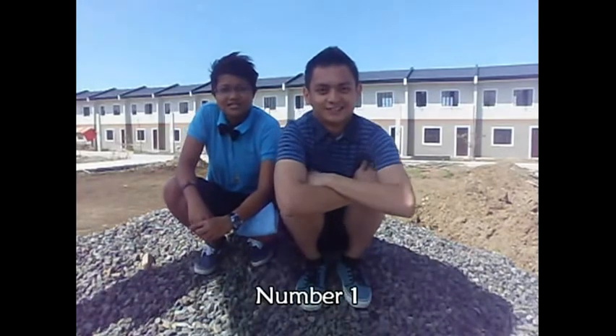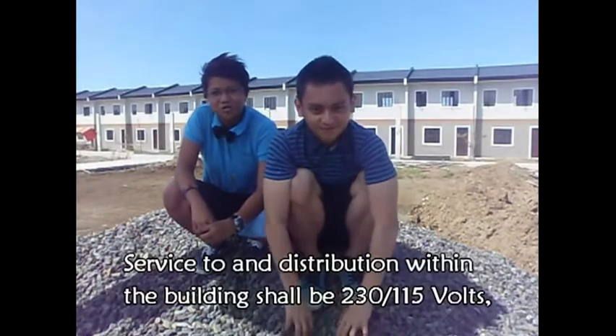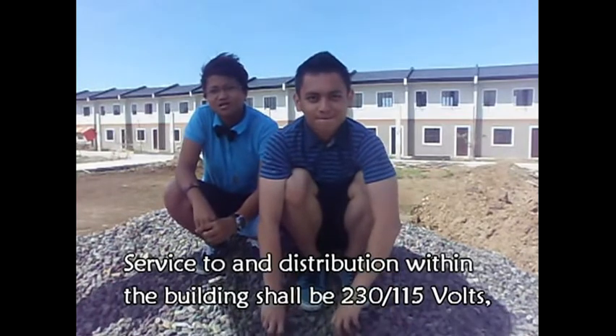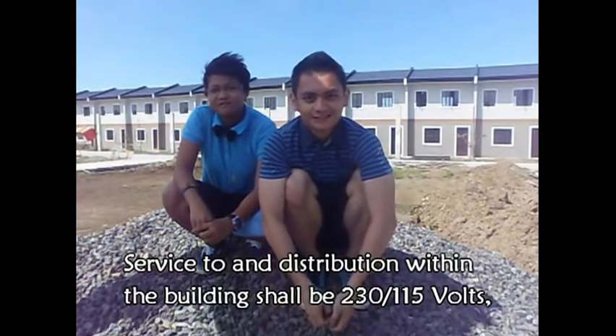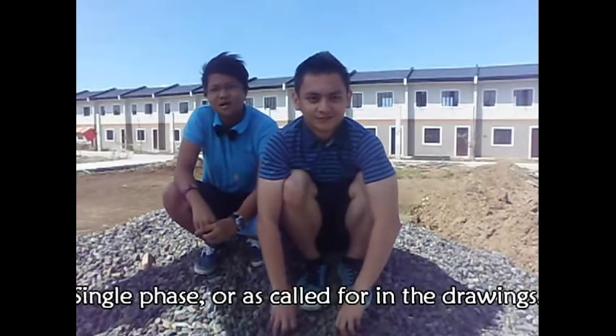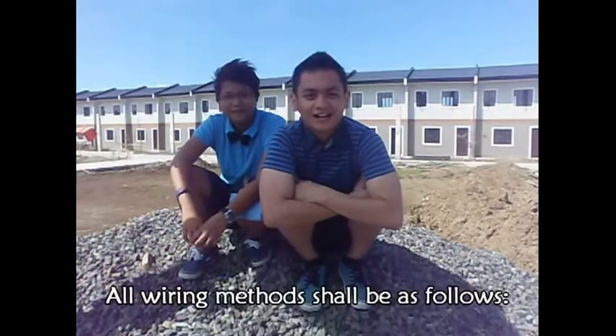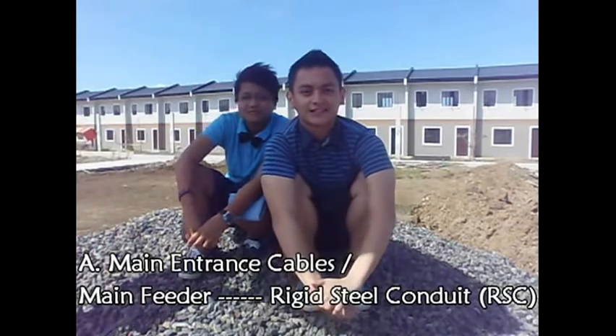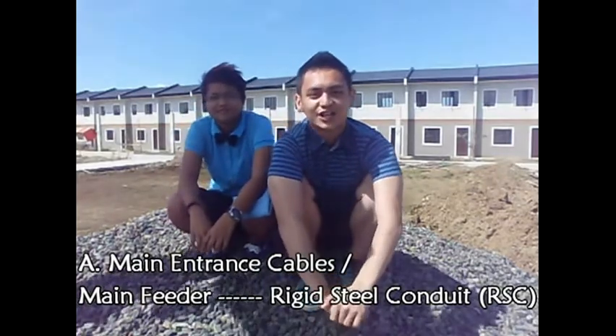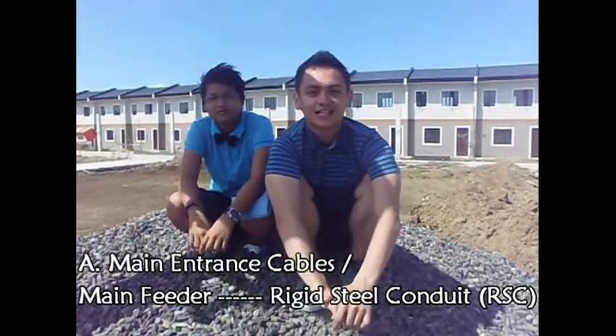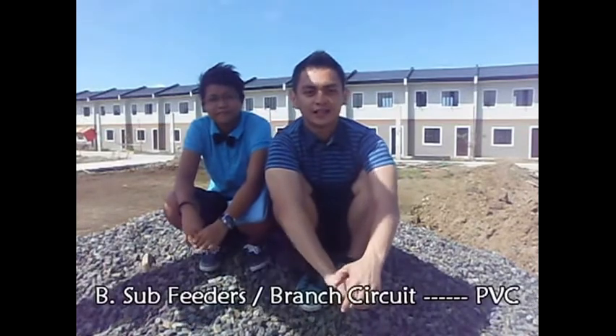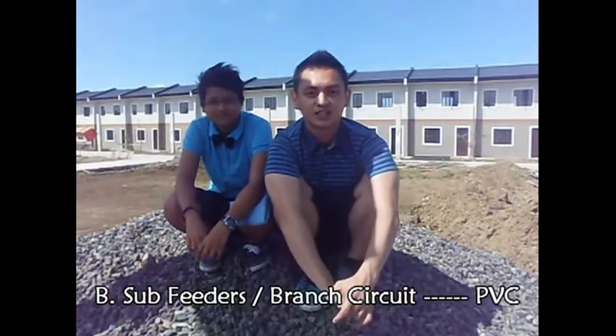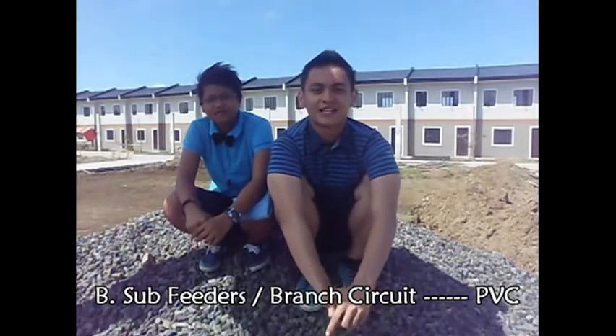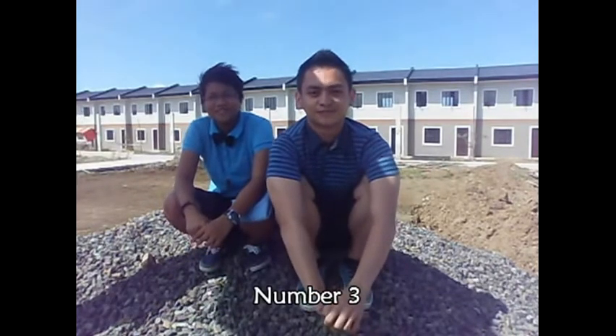Number 1. Service to and distribution within the building shall be 230 over 115 volts, single phase, or as called for in the drawings. Number 2. All wiring methods shall be as follows. Letter A. Main entrance cables, main feeder: rigid steel conduit, RSC. Letter B. Sub-feeders, branch circuit: PVC. Number 3.